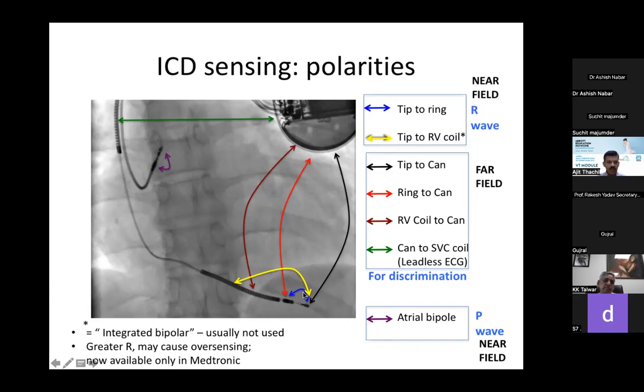Now, there is also something called an integrated bipolar, which is rarely used these days, wherein you can measure the R wave from the tip to the RV coil. This is usually not used these days. It can give a bigger R wave than the true bipolar R wave, but it may cause oversensing. It's currently available only in Medtronic and generally not used, so I won't discuss that.